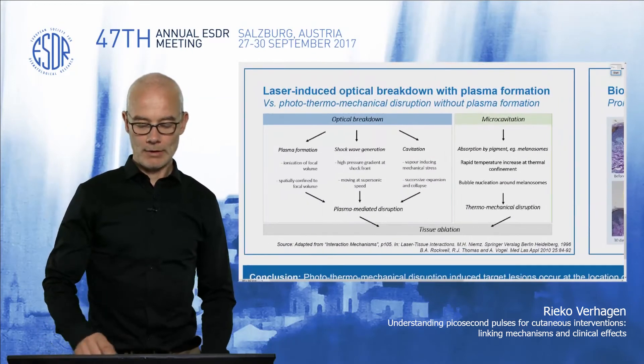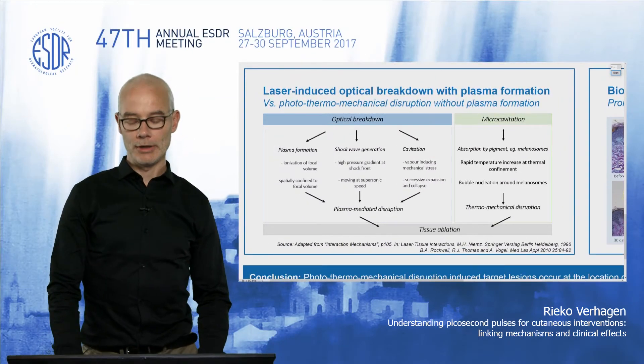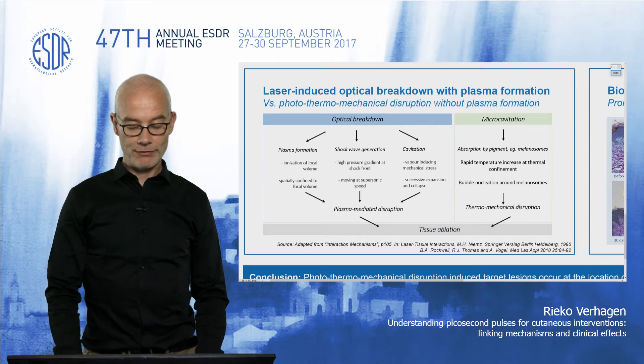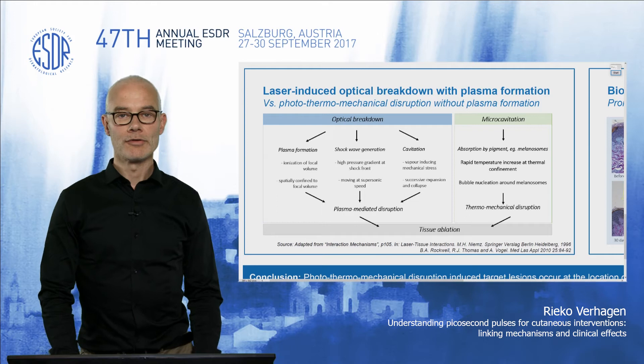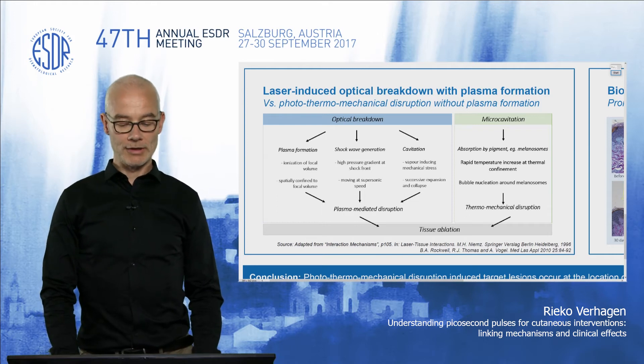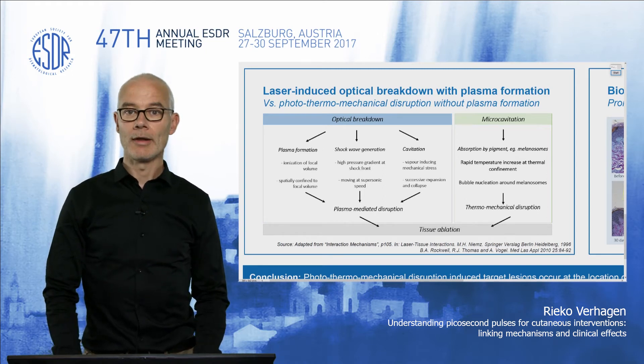Either way, all these mechanisms will lead to some form of tissue ablation. However, the path along which that happens is quite different for different technologies, and therefore the target they actually treat can also be quite different. For pure laser induced optical breakdown the target is chromophore independent, so you can treat at any arbitrary depth where you can reach sufficient intensity. For the microcavitation-driven mechanism there is a need for an absorbing chromophore which actually initiates the effect.